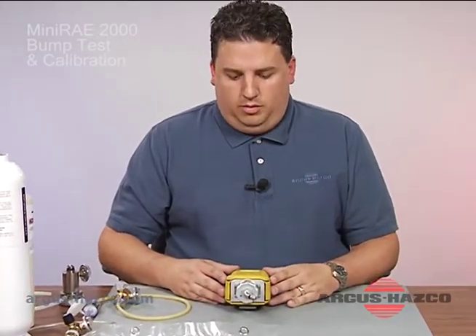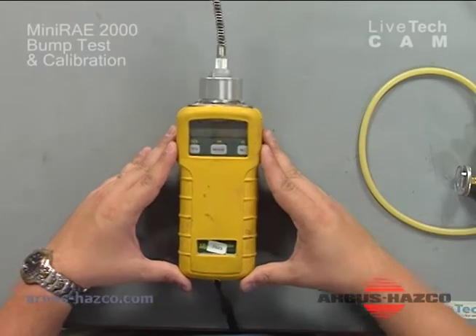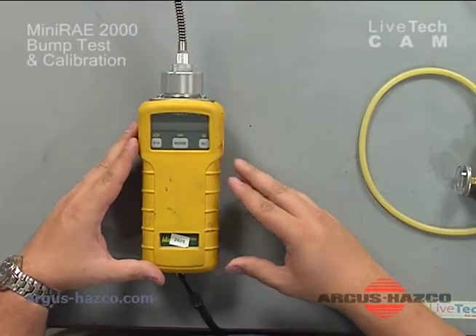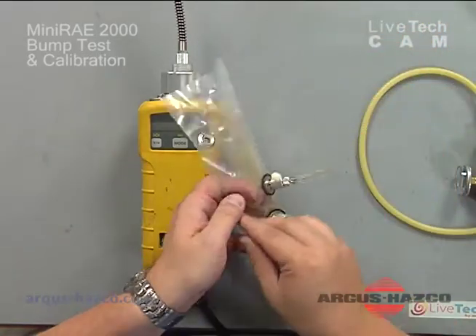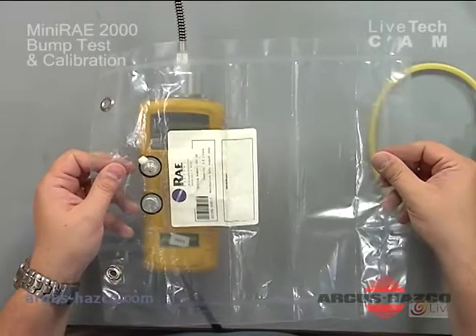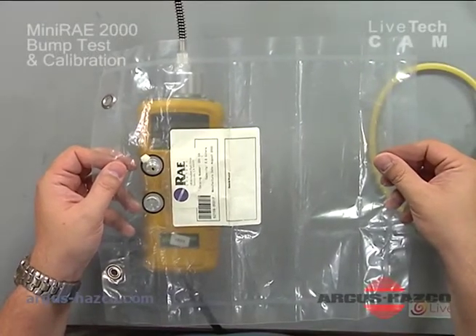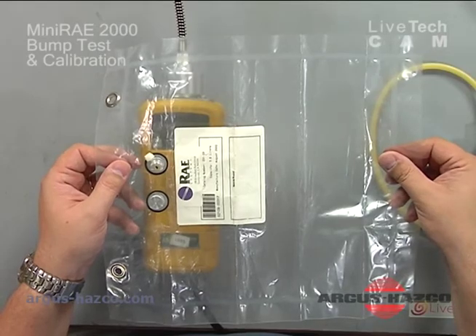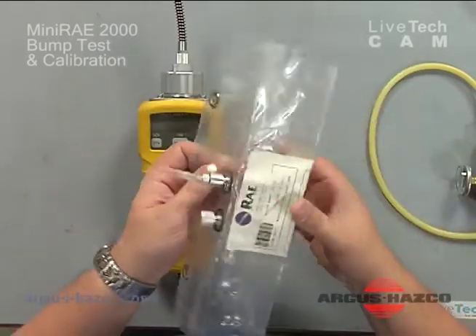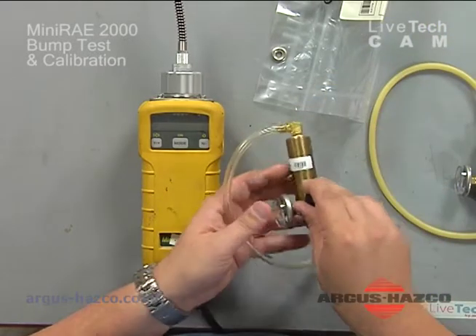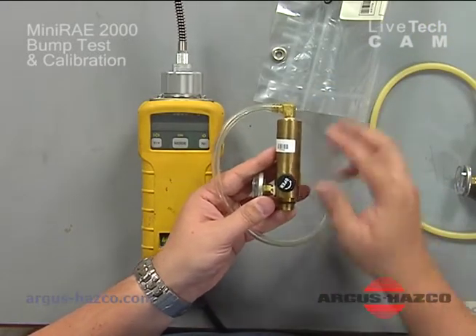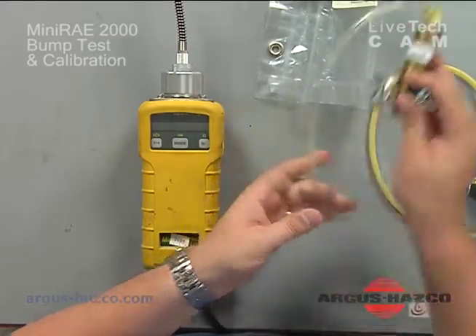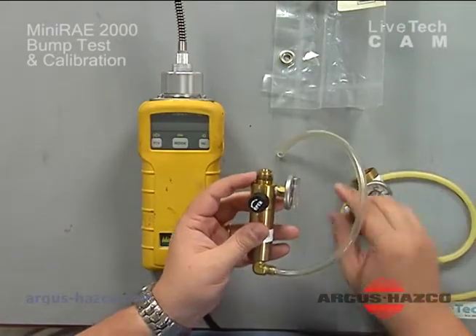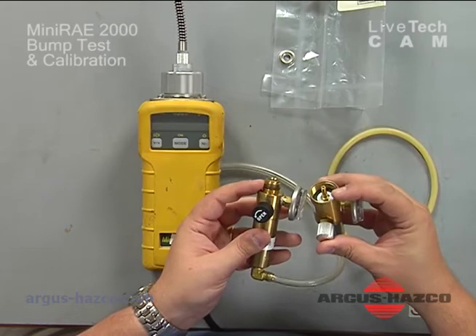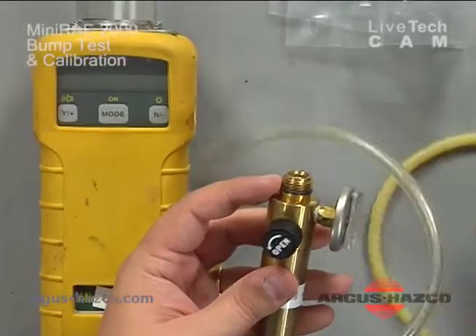So in this scenario, you will need the MiniRAE 2000, and there are 3 different regulator types that you could be using for this. You could use a calibration bag, which you fill with your gas sample and let the MiniRAE 2000, since it has a pump, suck that sample out of the bag to the PID sensor and lamp in order to calibrate or bump test. You would need a 6 liter per minute regulator to hook up to your cylinder to fill that bag fairly quickly. You have 2 different regulator types that have either a male fitting or a female fitting at the end, and that is dependent upon the size cylinder that you have with you.